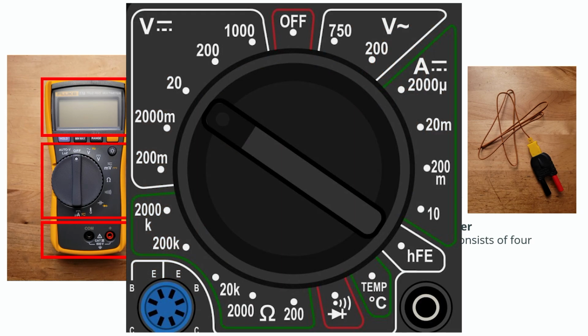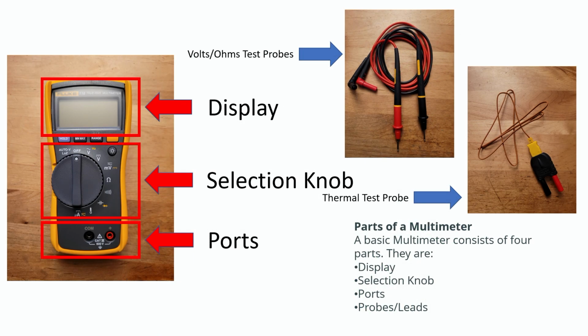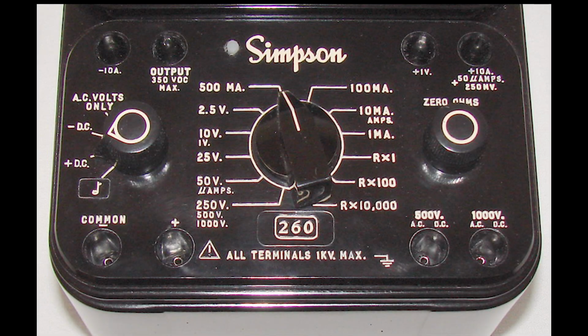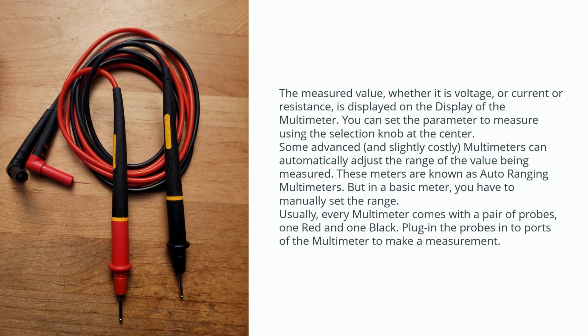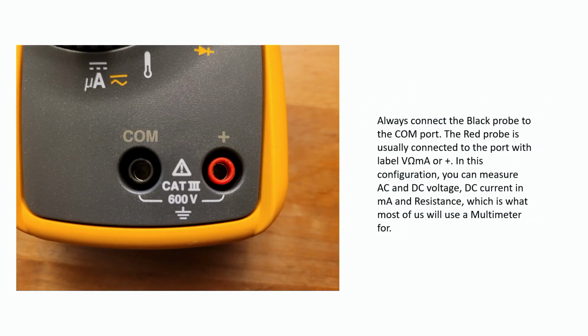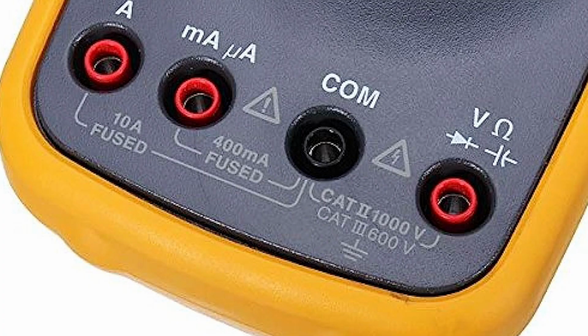You can set the parameter to measure using the selection knob at the center. Some advanced and slightly costly multimeters can automatically adjust the range of the value being measured. These meters are known as auto-ranging multimeters, but in a basic meter you have to manually set the range. Usually every multimeter comes with a pair of probes, one red, one black. Connect the black probe to the COM or common port. The red probe is usually connected to the port with a positive symbol, or volts, ohms, milliamps.